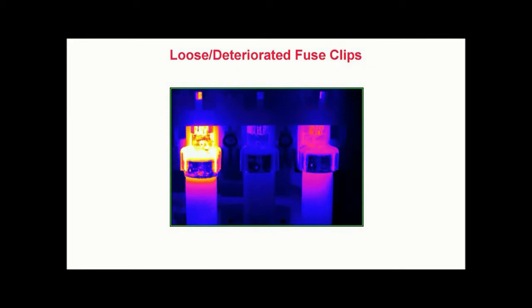Loose or deteriorated fuse clips. In this thermogram of a low voltage disconnect switch, we see excess localized heating caused by loose or deteriorated fuse clips on the left and right fuses. This problem is common to low voltage devices and can lead to an unscheduled outage.